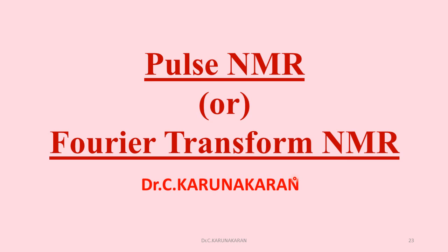The advantage of pulsed NMR is that the NMR measurement is completed in seconds, less than seconds, whereas in the case of the continuous wave NMR spectrometer, the older version, it is time consuming. We'll see further.